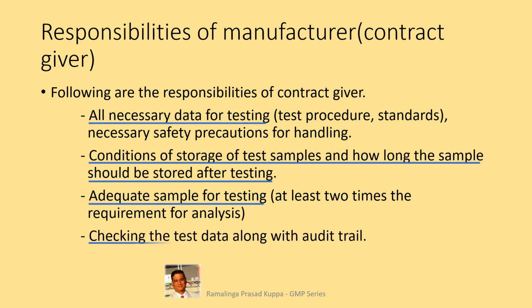Checking the test data along with audit trail. Data reviews along with audit trail for both electronic and non-electronic equipment should be done. Audit trail for non-electronic equipment can be checked through controlled logbooks for who, when, what, why of the operation.